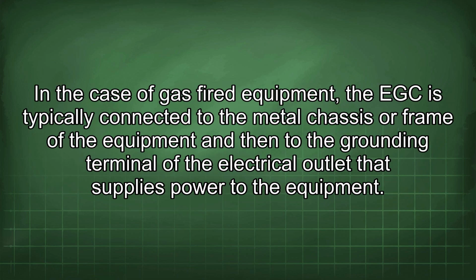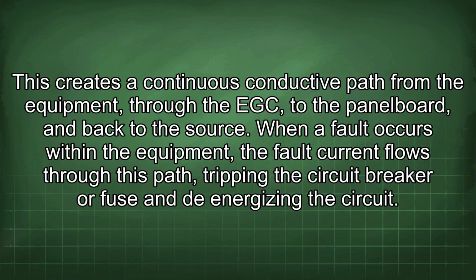In the case of gas-fired equipment, the EGC is typically connected to the metal chassis or frame of the equipment and then to the grounding terminal of the electrical outlet that supplies power to the equipment. This creates a continuous conductive path from the equipment through the EGC to the panel board and back to the source. When a fault occurs within the equipment, the fault current flows through this path, tripping the circuit breaker or fuse and de-energizing the circuit.